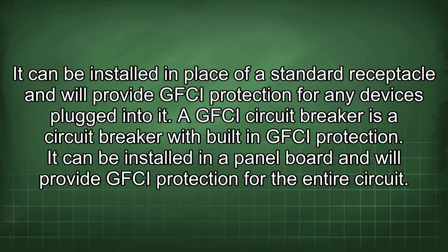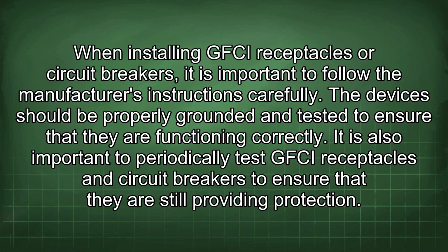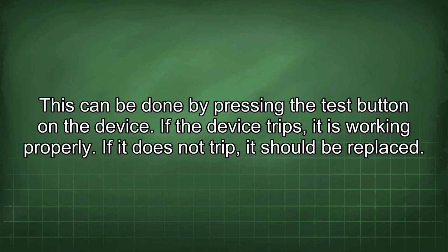It can be installed in a panel board and will provide GFCI protection for the entire circuit. When installing GFCI receptacles or circuit breakers, it is important to follow the manufacturer's instructions carefully. The devices should be properly grounded and tested to ensure that they are functioning correctly. It is also important to periodically test GFCI receptacles and circuit breakers to ensure that they are still providing protection. This can be done by pressing the test button on the device. If the device trips, it is working properly. If it does not trip, it should be replaced.